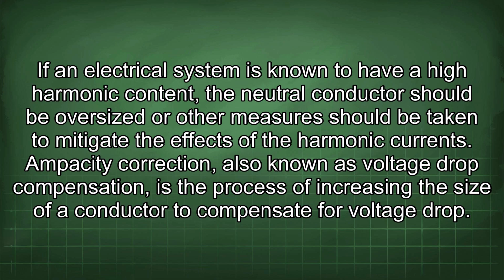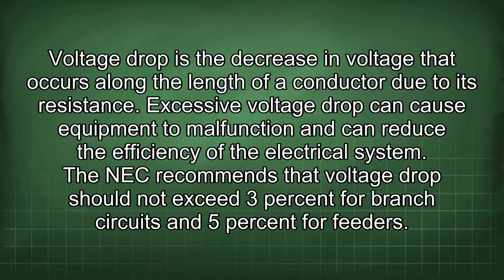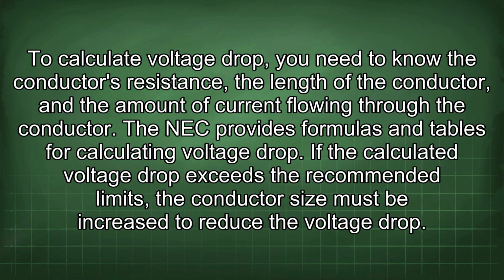Ampacity correction, also known as voltage drop compensation, is the process of increasing the size of a conductor to compensate for voltage drop. Voltage drop is the decrease in voltage that occurs along the length of a conductor due to its resistance. Excessive voltage drop can cause equipment to malfunction and can reduce the efficiency of the electrical system. The NEC recommends that voltage drop should not exceed 3% for branch circuits and 5% for feeders. To calculate voltage drop, you need to know the conductor's resistance, the length of the conductor, and the amount of current flowing through the conductor. The NEC provides formulas and tables for calculating voltage drop.